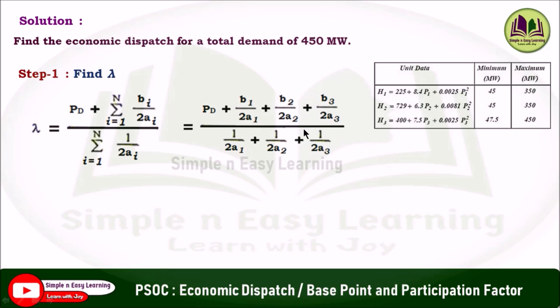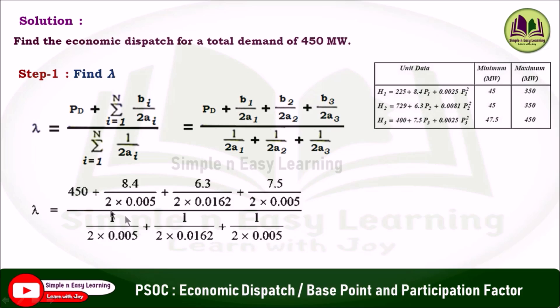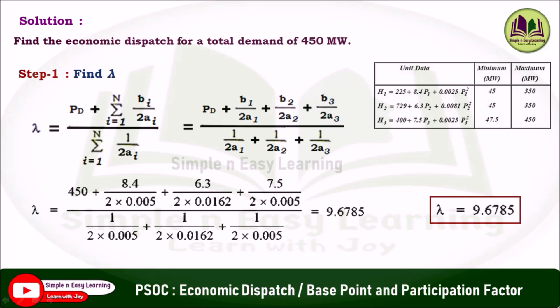Here, a1, a2, a3 are the coefficients of P1², P2², and P3² in the cost function, and b1, b2, b3 are the coefficients of P1, P2, and P3 in the cost function respectively. Substituting the values — demand is 450, b1 is 8.4 — and dividing through the respective 2a terms, we get lambda equal to 9.6785.